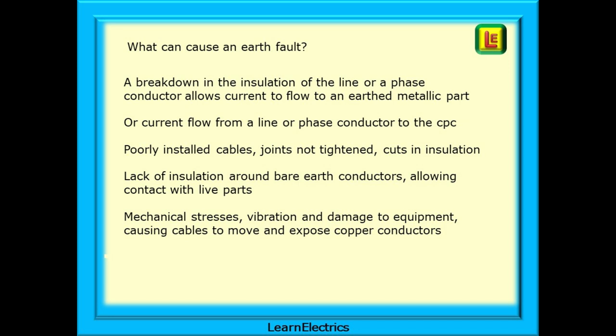Lots of things can cause an earth fault. For example, a breakdown in the insulation of the line or a phase conductor that allows current to flow to an earthed metallic part or current flow from a line or phase conductor directly to the CPC if they touch. Consider poorly installed cables, joints not tightened, cuts and lack of sleeving or insulation around bare earth conductors allowing contact with live parts is common. Then, there are mechanical stresses, vibration and damage to equipment causing cables to move and expose copper conductors or just wear the insulation away with continual prolonged vibration.